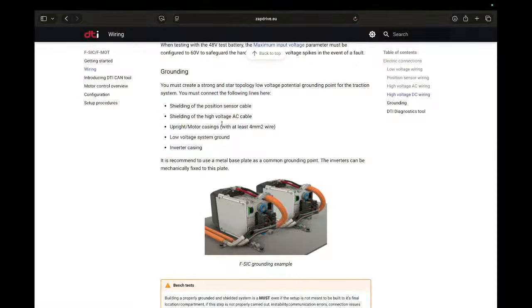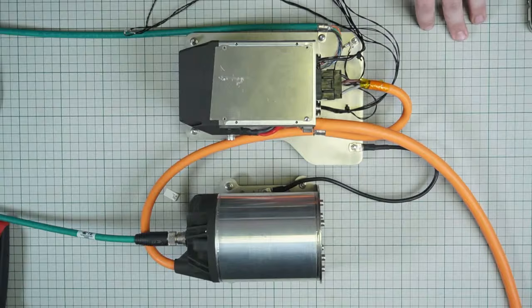So you should bring here all the shieldings and groundings of the system, including the low voltage ground. Technically, you connect the low voltage ground to the common plate, and all the shieldings and groundings of the powertrain system should be connected here. As well, if you are using other devices like control units and so on, you should put these units to the common potential via this plate. I will also show you around this specific plate that we have here as a mock-up, but you should use a very similar principle for your own applications.